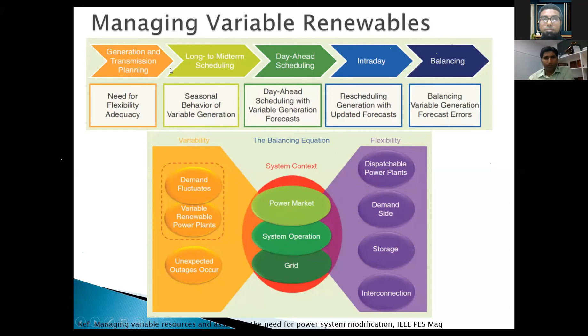On the distribution side that's the picture, but what about transmission? There's going to be quite a bit of probabilistic analysis required, because of variability from DERs and wind resources. Previously, engineers dealt with load uncertainty modeled as stochastic load, giving some certainty about load growth and where transmission lines should go. Now there's generation uncertainty as well as demand-side uncertainty, which becomes a real issue. We've proposed ideas on probabilistic contingency analysis to come up with optimal policy to maintain system stability at the bulk level.